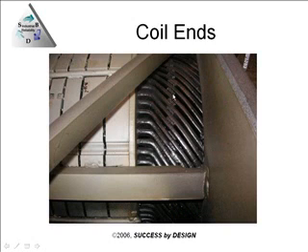Those are each folds of electrical insulation tucked between the coils. Well, with that much distance, I should have seen far more of that. Usually in a length like this, I would have put one close to the knuckle coming out, one in the middle, and one towards the end, in order to keep the coils from coming very close to each other. If they come too close, they'll short if the insulation system is wearing out.